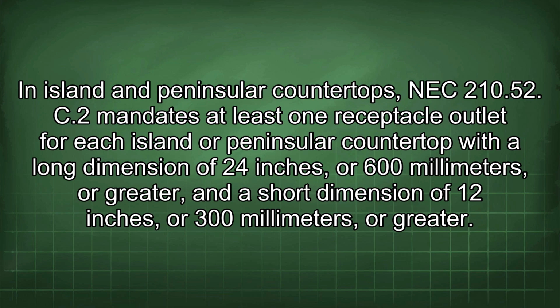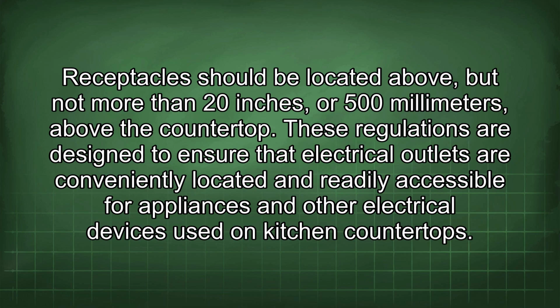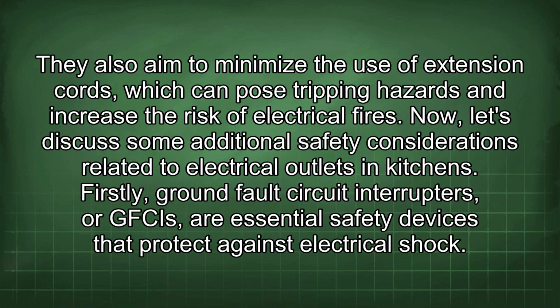In island and peninsula countertops, NEC 210.52(C)(2) mandates at least one receptacle outlet for each island or peninsula countertop with a long dimension of 24 inches, or 600 millimeters, or greater, and a short dimension of 12 inches, or 300 millimeters, or greater. Receptacles should be located above, but not more than 20 inches, or 500 millimeters, above the countertop. These regulations are designed to ensure that electrical outlets are conveniently located and readily accessible for appliances and other electrical devices used on kitchen countertops. They also aim to minimize the use of extension cords, which can pose tripping hazards and increase the risk of electrical fires. Now let's discuss some additional safety considerations related to electrical outlets in kitchens.